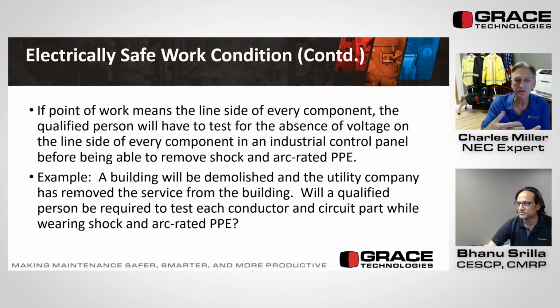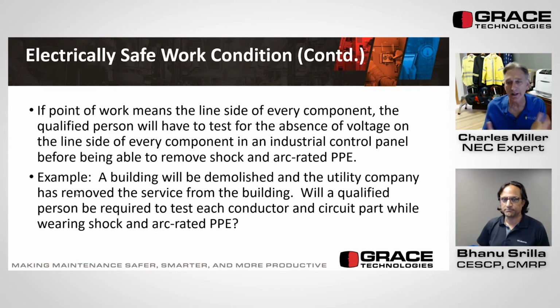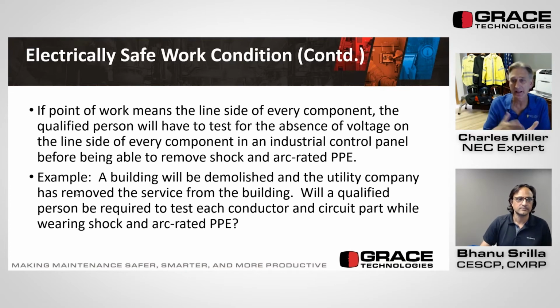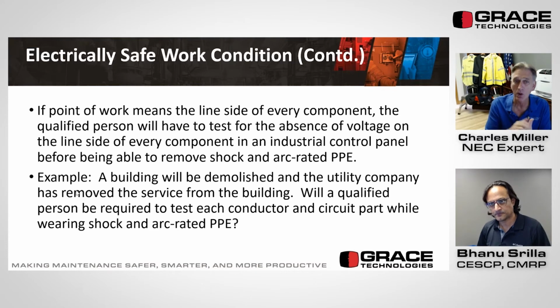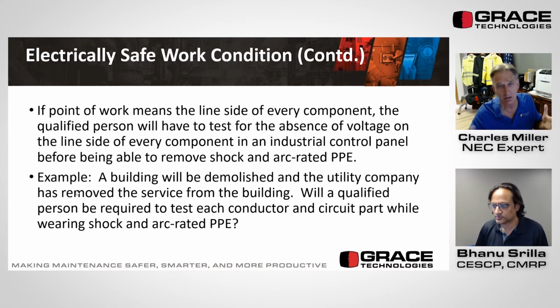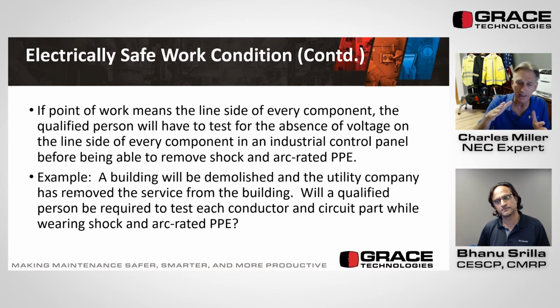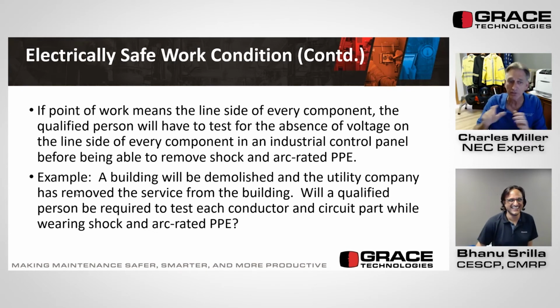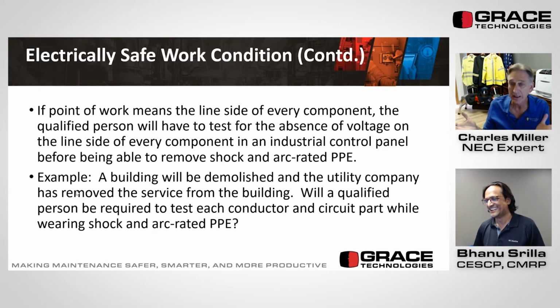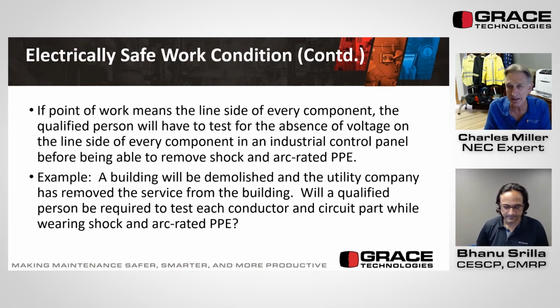All right, this is again things we've already talked about: point of work, every line side of every component, and a qualified person. If that's true, they'd have to test every component in an industrial control cabinet, or when it's installed, or along the way you're going to have to buy half a dozen safe test points from Bhanu to put in that cabinet so you can do this all from the outside. I did talk about the example where a building's demolished, the utility company completely removes the wiring, but yet a qualified person is going to have to test each conductor, each circuit, each device inside that building.